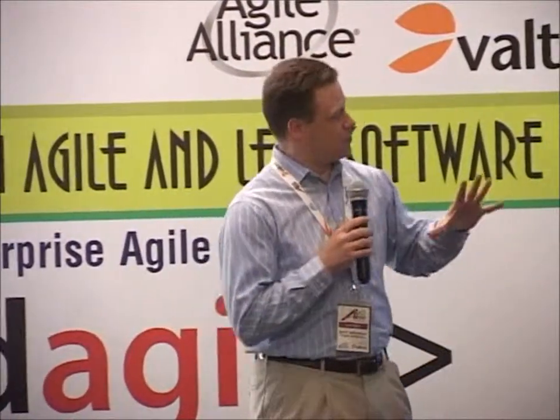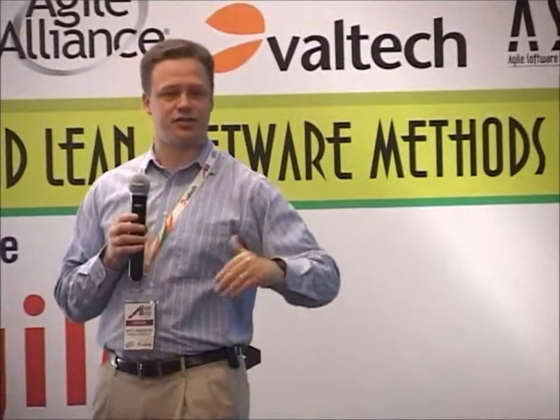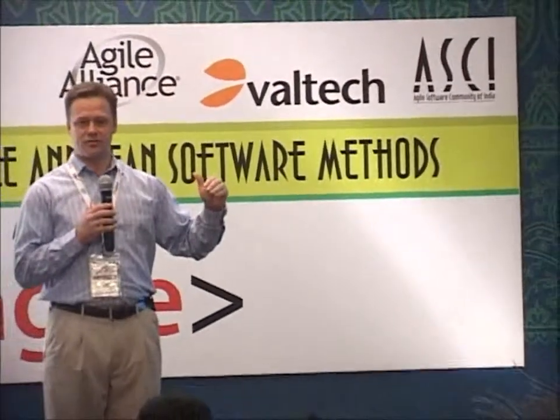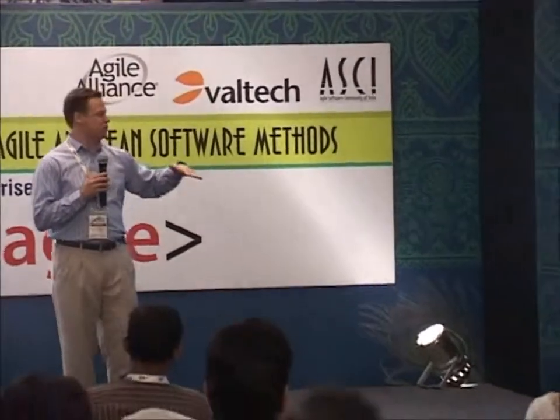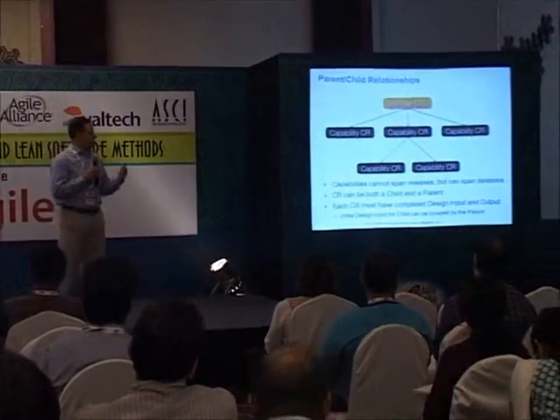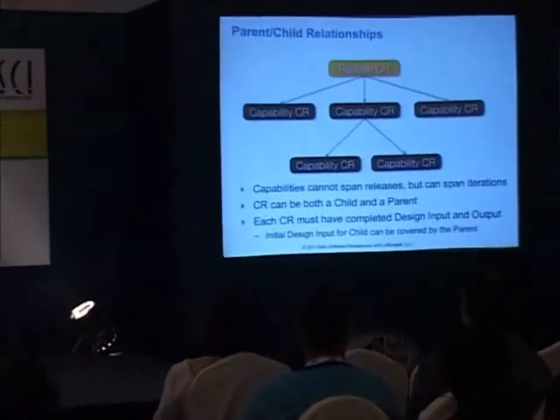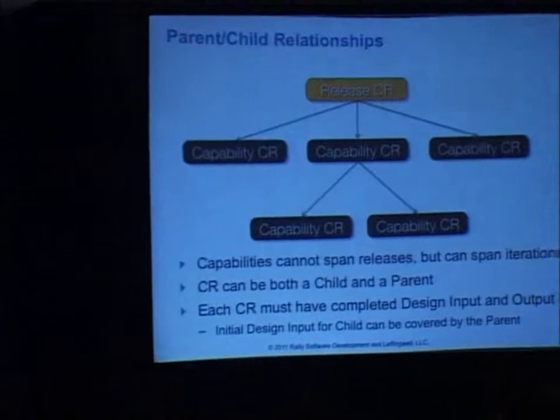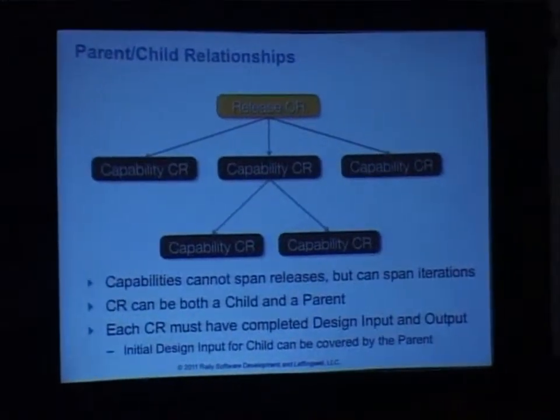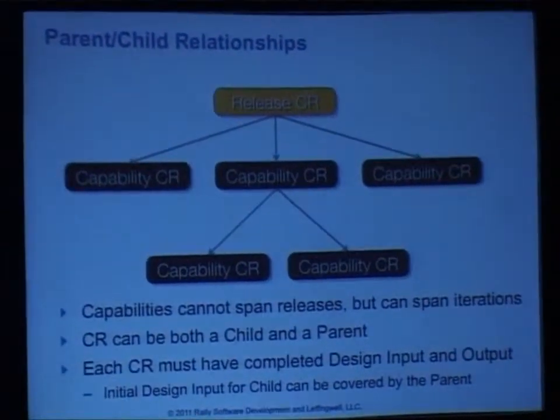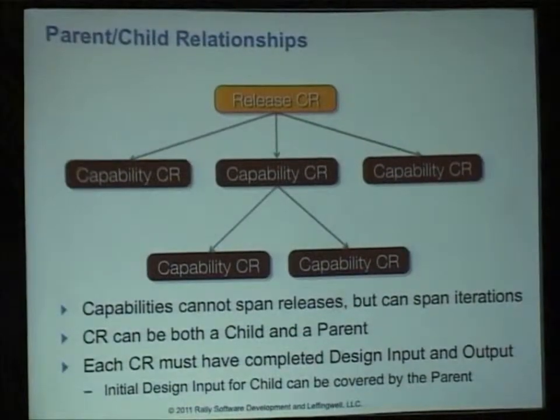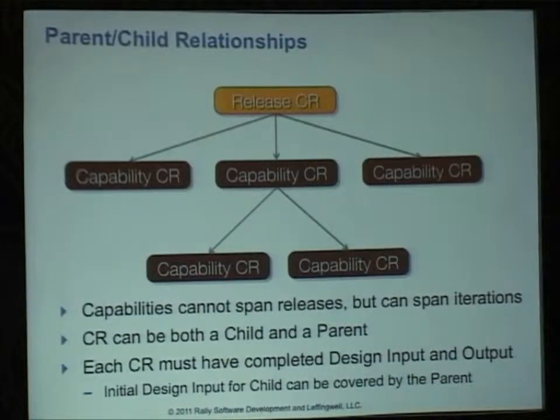With that in mind, you might have kind of a hierarchy of CRs. I can have a release CR way up top, which is where our final signatures are, and that's where we expect to be audited. But I can have these children CRs, and they can even have children, grandchildren, and so on. The philosophy behind it is, my parent, if I've signed off on it, can actually serve as the initial design input for any of the children. From a traceability standpoint, as we've worked with the FDA, they've been fine with this.